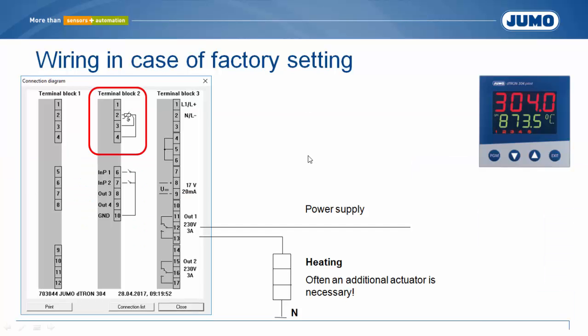The factory setting of the controller configuration is suitable for the following application: measurement of a temperature at input number 1 with a RTD temperature probe PT100 in 3-wire circuit. The controller controls the temperature as two-state controller. Operation of the heater via the contact of output number 1. In many cases, changing of the configuration is not necessary. In the case of another application, the setting of the controller is possible in the configuration level.